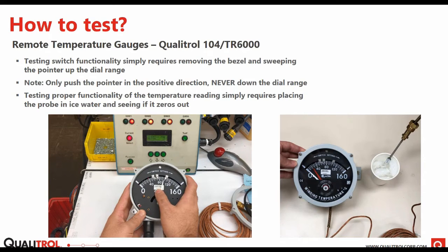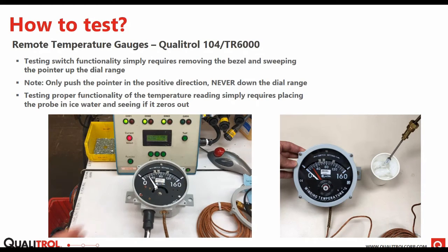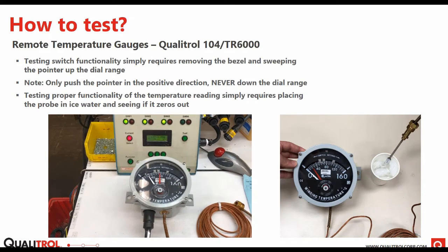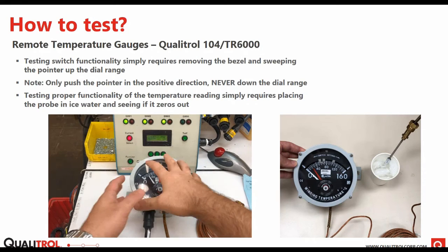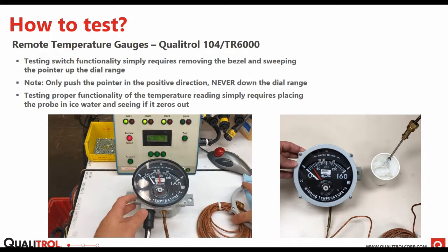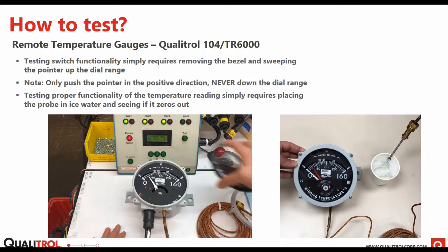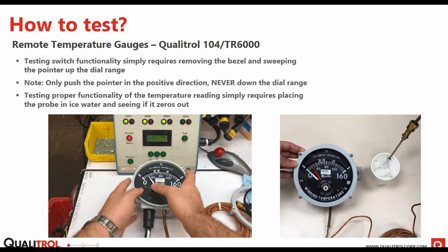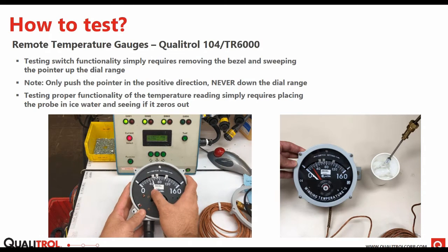So I'm just letting that glide down the dial range because it is spring loaded and it'll return back to that original place. But it's no problem to push it up the dial range and actuate those switches. And that's a real quick and easy way to test that all those switches are functioning and that they're actually going off at the desired temperature.